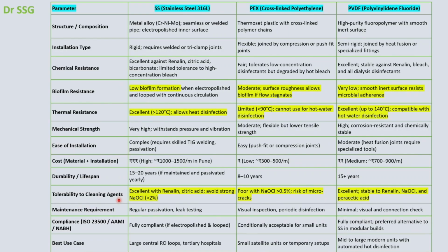So stainless steel tolerates heat. It gives excellent results with Renalin or citric acid, but it is less tolerant to bleach, that is sodium hypochlorite. So there is a risk of corrosion when you use hypochlorite. PEX poorly tolerates bleach and can withstand temperatures up to 60 to 65, not more than 85. PVDF is the best of what is available in flexible piping. It is resistant to bleach as well, but not much used here. So going forward, which one would you go for?